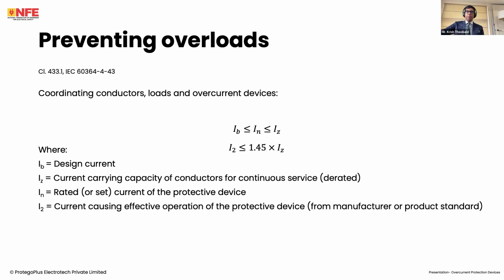Let me give you an example. I saw an installation in Hyderabad, and IB, which is the design current, was about 100 amps. The cable was 35 square mm. Let's say after derating it could also carry 100 amps, no problem. So you think, okay, it's fine. However, when I went and looked at the protective device, it was actually a 630 ampere MCCB. So that protective device is actually providing no overload protection in any manner.